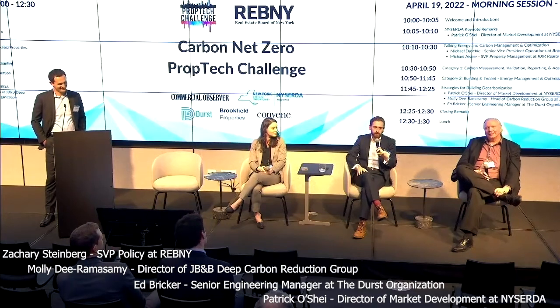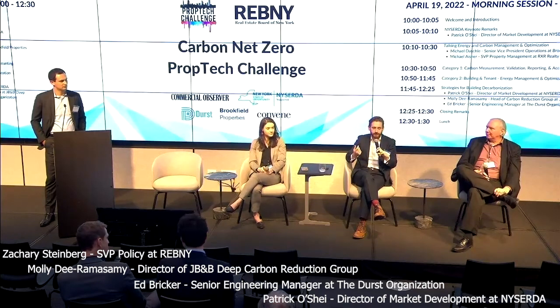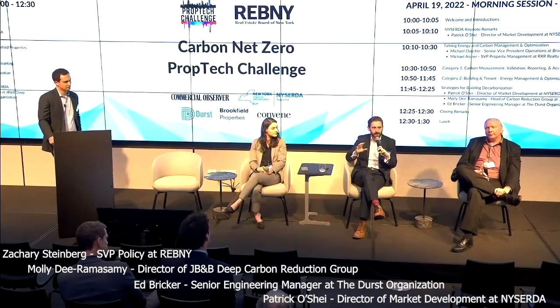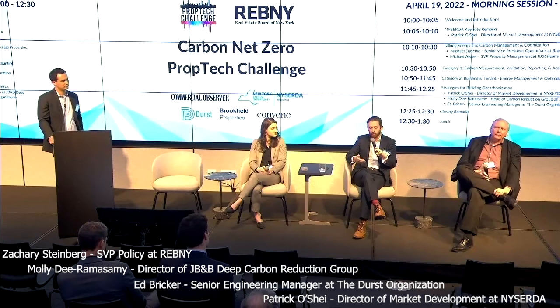The resolution you're going to look for, realistically, if you have 15-minute data, that's beautiful, but hourly data typically cuts it pretty well. Beyond that, you start to have a lot of trouble if you're trying to do anything with heat recovery, thermal storage, etc. It gets really tough to break down the resolution to get to the sizing criteria you need on the CapEx cycle to economize that decision. Anything less than an hour, and you start relying more on the energy model than on historical data.